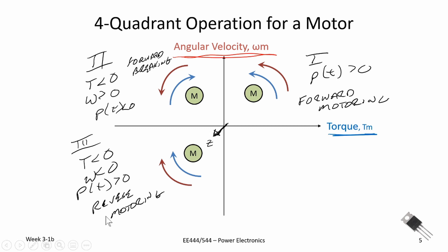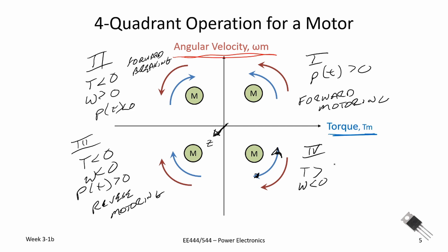Finally in the fourth quadrant, our torque is positive and our angular velocity is negative — let me fix the arrow on the torque there. In quadrant four, torque is positive, angular velocity is negative, and our instantaneous power is also negative. This is called reverse braking. In this quadrant the motor is providing energy back to the system; if we are braking we could do regenerative braking to recapture that energy, or we lose it as heat through resistive braking. Those are the four quadrants of operation for a motor.